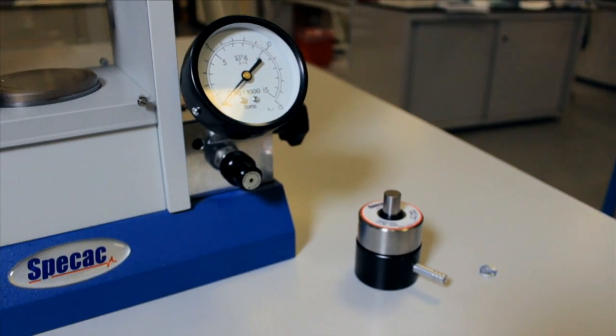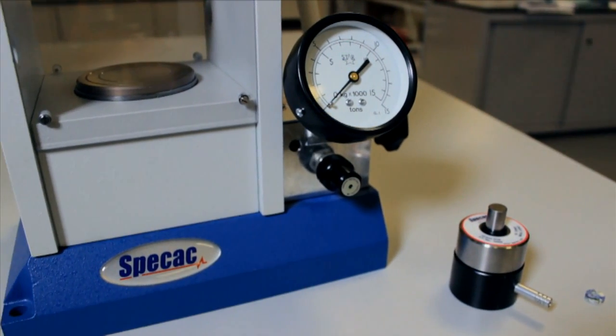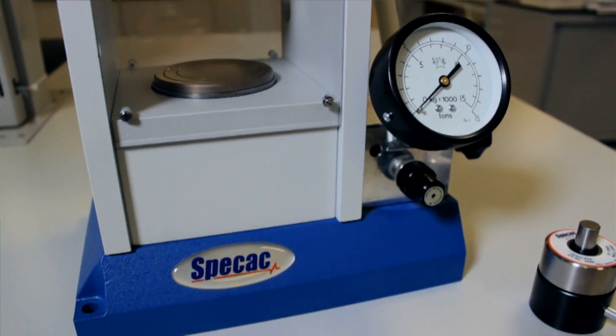This feature prevents accidental over-pressurisation of the work. The SPECAC manual hydraulic press is a very versatile, easy and robust piece of equipment for a wide variety of pressing applications. With the use of evacuable pellet dies and film making equipment, the press can be converted to construct and make pellets and films of different sizes for a similarly wide variety of pressing applications. Thank you for watching and keep a lookout for further video presentations from SPECAC.